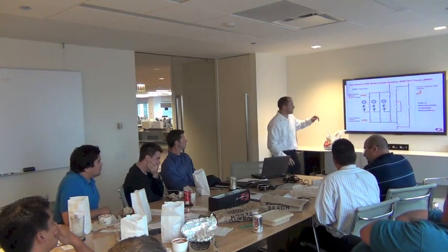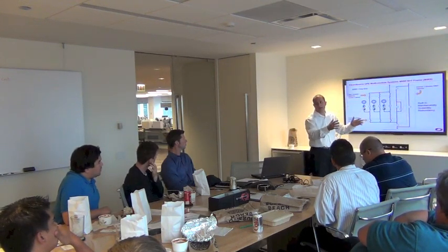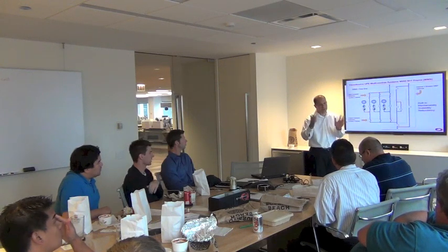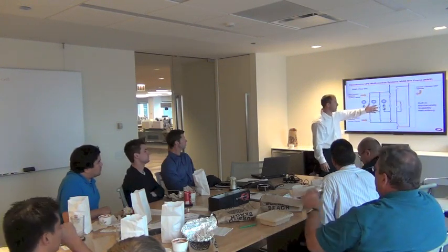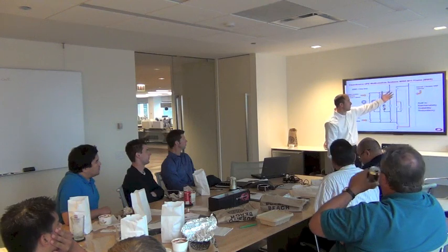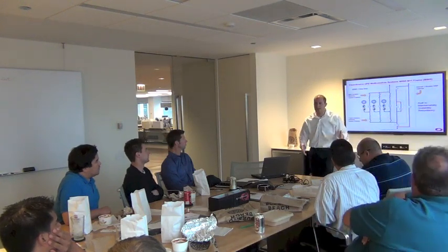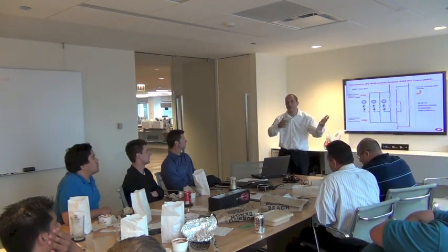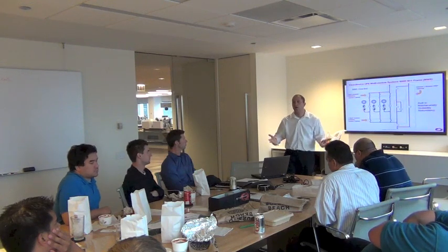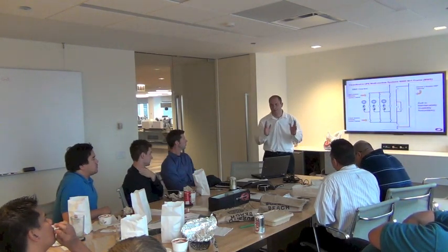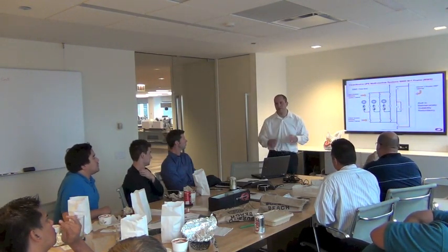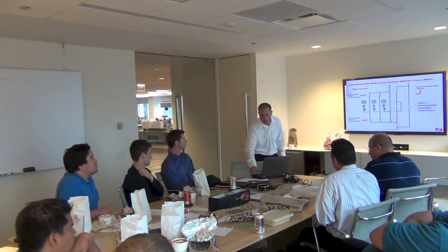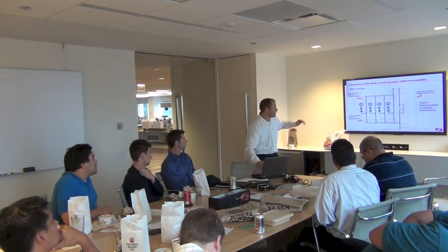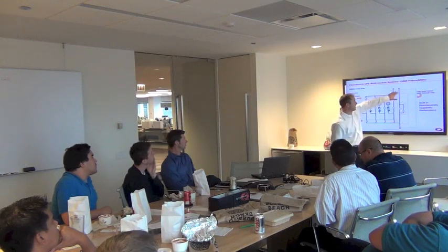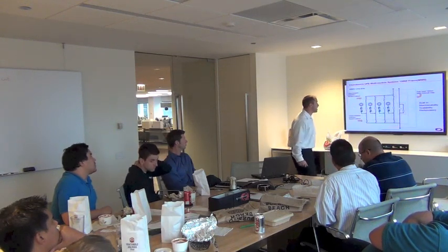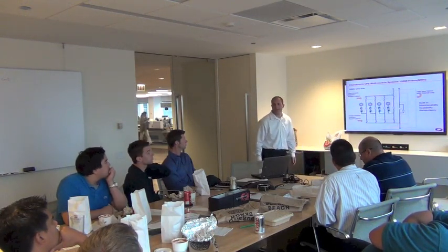The main difference is, with the G series and Z series, they look the exact same from the outside. If you look at a 600G and a 600Z, it's going to look the exact same. The main thing is just the bus work is smaller. Obviously, it's 800 amps. You also have room for a 3-breaker maintenance bypass in the I/O cabinet. With the Z series, that's going to have to be in the external distribution, or we can also provide an external 3-breaker maintenance bypass. There's just not enough room in the I/O cabinet to fit the breakers. So this would be basically a 1200Z. There's no room in here for a 3-breaker maintenance bypass, but same topology as the G series.